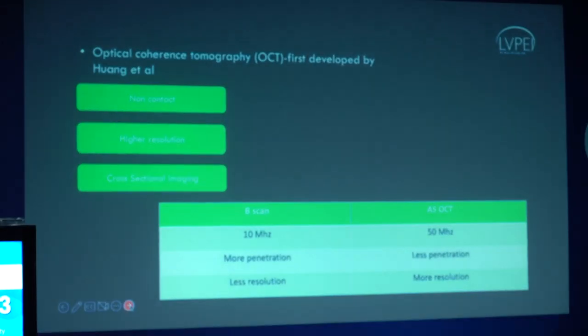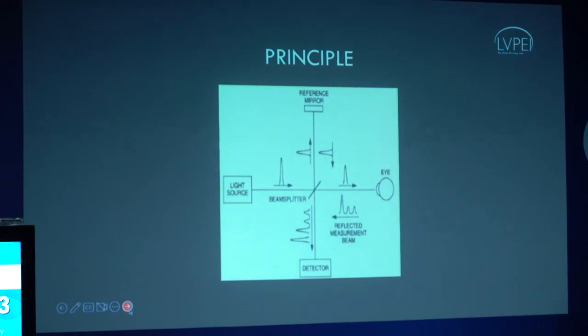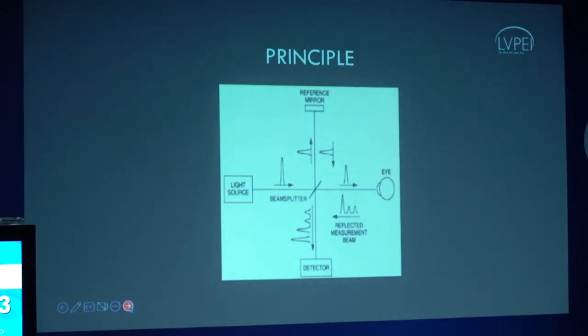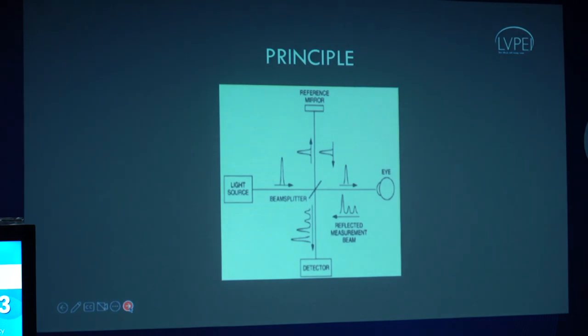OCT was first developed by Huang et al. as a non-contact method to provide higher resolution cross-sectional imaging. It refers to B-scan primarily in having a higher frequency, although it has less penetration but in turn gives better resolution. The principle is based on Michelson's interferometry, where the light source is received by the beam splitter and then reflected onto the reference mirror, which can be measured at variable depth to obtain the image of our choice.